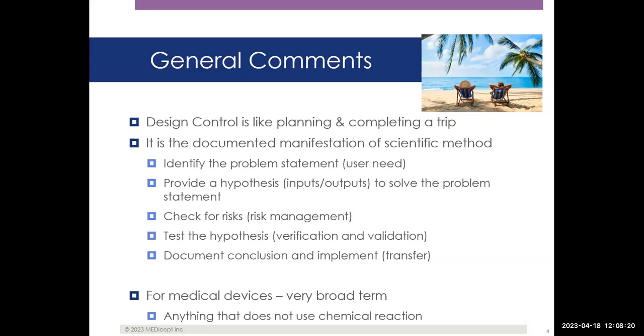One thing to point out is that design control is commonly thought of as for medical devices, and individuals often say, 'I'm not creating a medical device, I'm creating a scaffold for a cardiac product.' The term medical device is actually a very broad term in the FDA and ISO's world — anything that doesn't use a chemical reaction could be considered a medical device subject to design controls. Even with that said, design controls in some facsimile have reached pharmaceutical development, and the requirements to document inputs, outputs, risk management, and verification testing are now in pharmaceutical development as well.